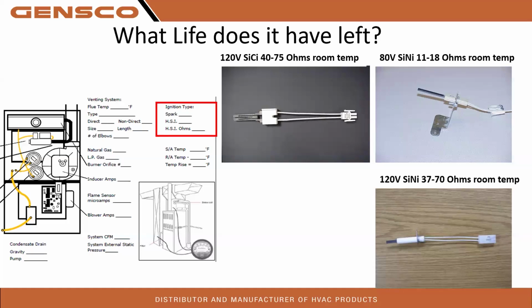So we have ohm ranges for them, right? 120 volt silicon carbides, 40 to 75 ohms at room temp. So what's this going to tell us if we're doing this as a tune-up? Well, if we have 100 ohms, 100 plus, maybe 150, that igniter's getting ready to go. We also have 80 volt igniters, silicon nitride, 11 to 18 ohms at room temp. This is essentially going to be the same thing: if we have 26 ohms, that igniter's getting old, it's going to have a problem.